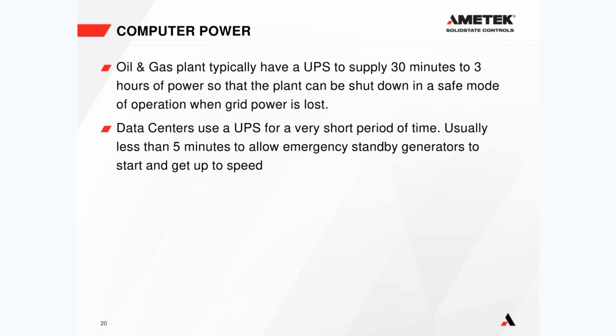In a data center, the data center's UPSs are only used for a very, very short period of time, usually less than 5 minutes. And all that time is for is to allow the emergency standby generators to start and get up to speed. So pretty much every data center has a huge bank of emergency standby generators rated to power their whole plant. And if grid power goes off, the UPS's only responsibility is to keep power to the connected equipment until the emergency standby generators get up to speed and are safe to put onto load. So that's the two main differences between petrochemical and data centers.